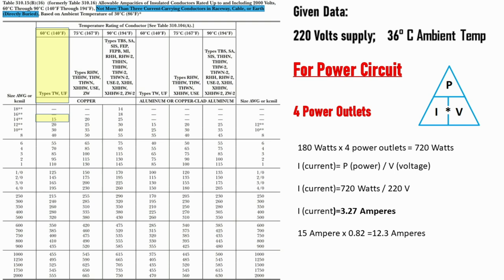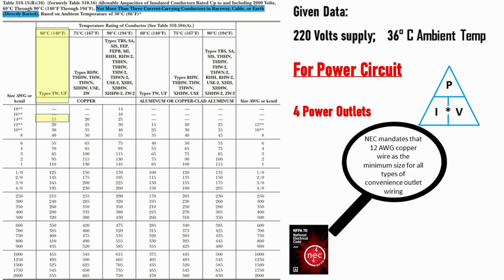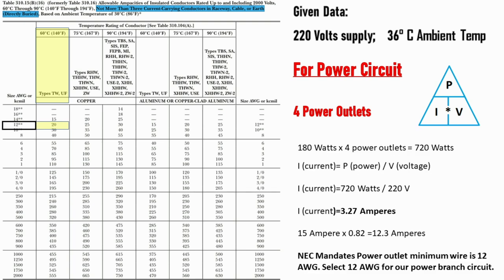Going back to the table, we could select 14 AWG. However, NEC mandates 12 AWG copper wire as the minimum size for all types of convenience outlet wiring. So we select 12 AWG.